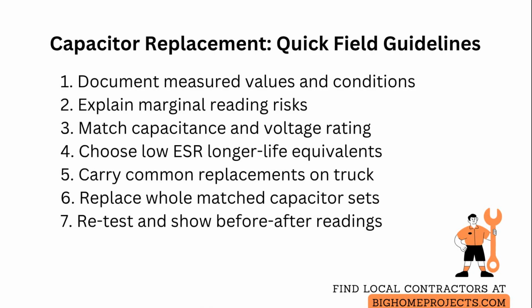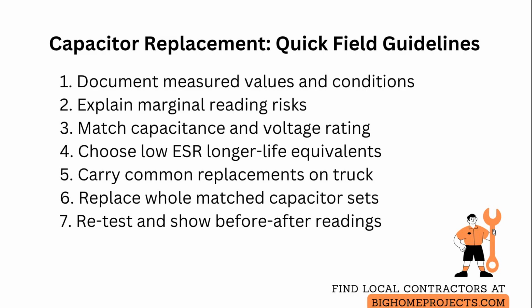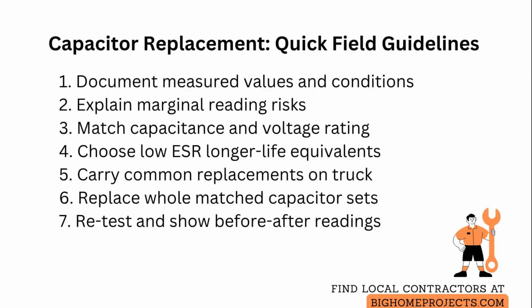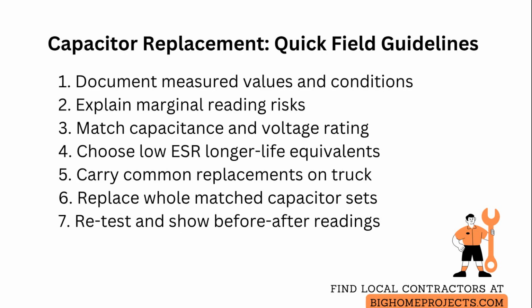Carry commonly used replacement values on the truck and install a new part immediately if the device is critical to system operation or safety. If the capacitor is part of a match set, replace the whole set to maintain reliability and avoid accelerated failure of adjacent parts.